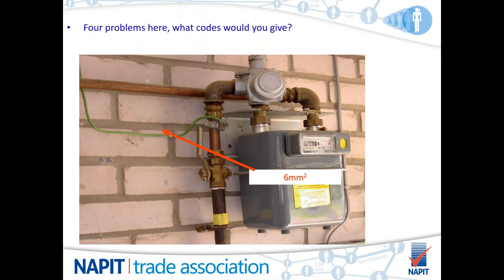It would depend, firstly, on the type of earthing arrangement you've got, whether it's TN-S or TN-C-S. Obviously, with a TN-C-S system, we have prospective fault currents able to reach a much higher level, and this conductor needs to be able to take those prospective fault current levels. It's a possibility that you could do a calculation, the adiabatic equation, to prove that it was okay. At the time, I must agree, C3 is probably the code that I would go with here.